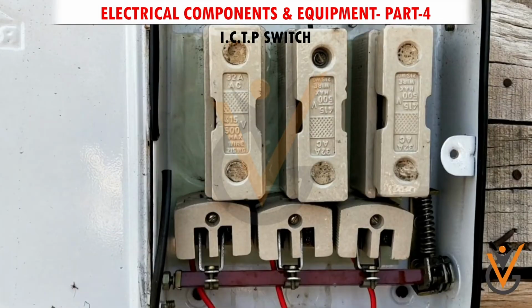ICTP switch. Iron-clad triple-pole main switches are used to control the 3-phase supply circuit. These are available in 15 amp, 30 amp, 60 amp, 100 amp, 150 amp and 250 amp current ratings. Generally these switches are also known as 3-phase 4 wire main switches. In these switches 3 fuses and a neutral link are available. The neutral wire is directly connected with the neutral link and the phase wires are connected with these fuse links.